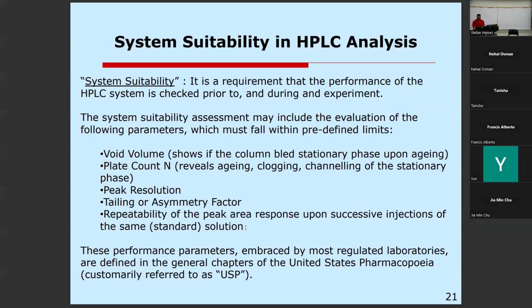And you also want to make sure you're getting repeatability of your peak area response upon successive injections of the same solution. So I put the same one in over and over again. I should get the same area response. The integration of the peak should be the same every single time I send it through. So every time you do a standard, it should run the same. These are your system suitability assessments.